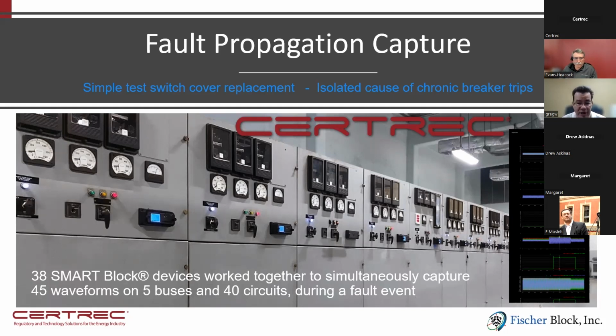And if it's an electromechanical relay, you have no waveform to look at in order to determine why the breaker tripped. Was it a malfunctioning relay? And so forth. So in this case, we're providing visibility to the customer in terms of when a breaker does trip. However, in this case, our utility customer was getting numerous nuisance trips whereby one breaker would trip and then it would cause flickers and maybe other breaker trips on other buses and feeders. And so we installed 40 devices as retrofit covers on those test switches. So no wiring. We just have spring-loaded pins underneath, doing all the voltage monitoring, just with 2 thumb screw replacement of a cover. No outage install here.